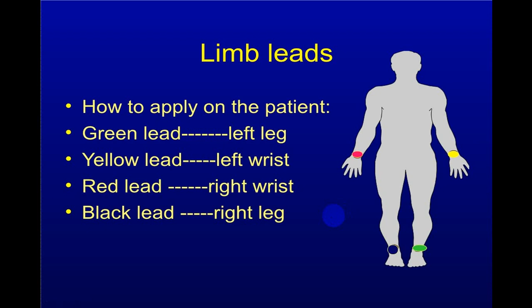Normally there are 4 standard limb leads. Green is attached to the left leg, black is attached to the right leg, red is attached to the right limb, and yellow is attached to the left limb. These are standard colors, but even with that you should read the lead, because on the lead it is mentioned RA, LA, RL, LL. You should read those and attach accordingly. If there is a malposition of these leads, it will result in an abnormal ECG.